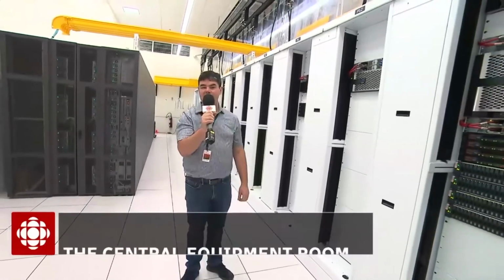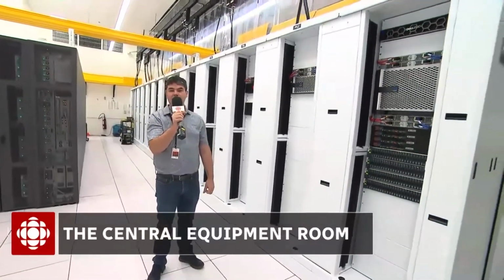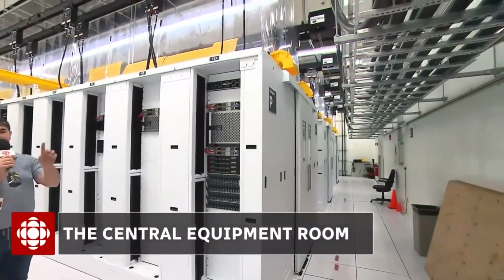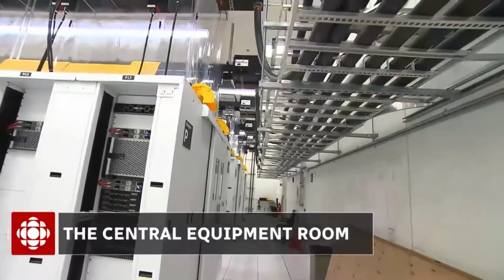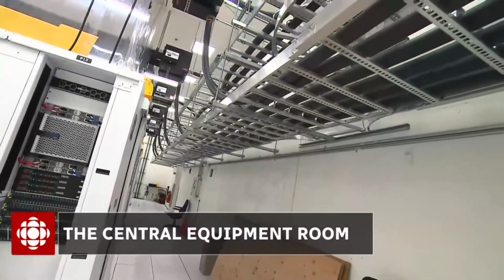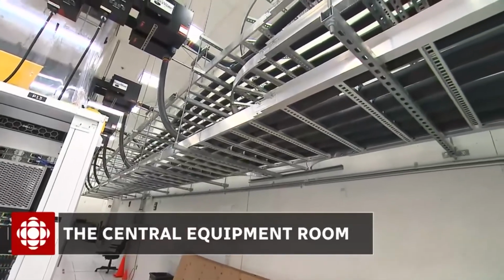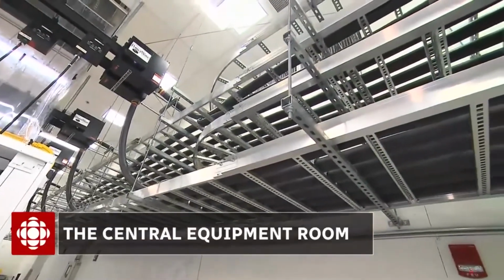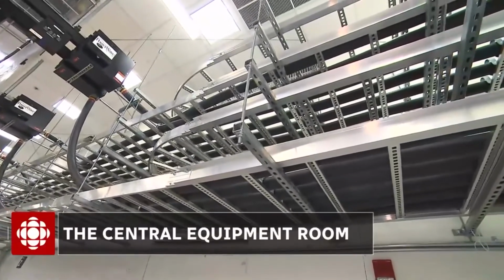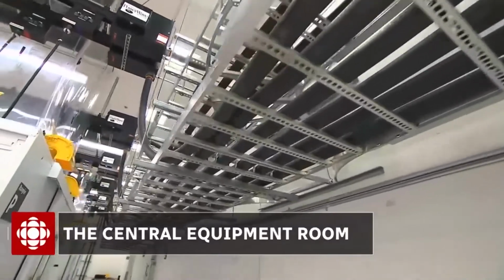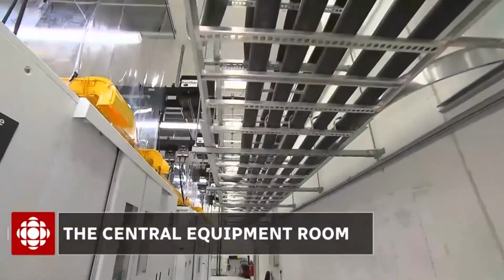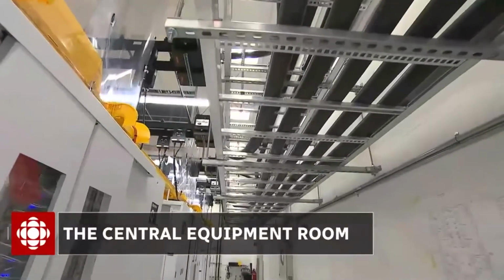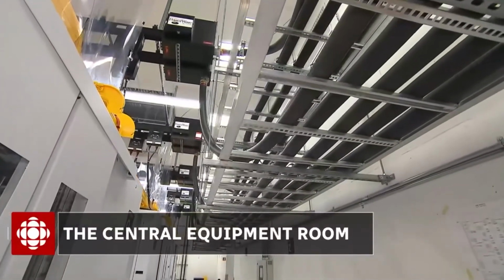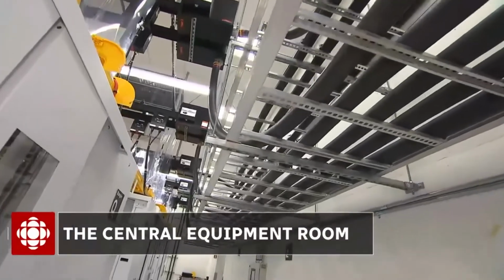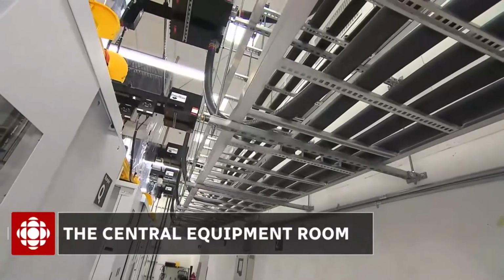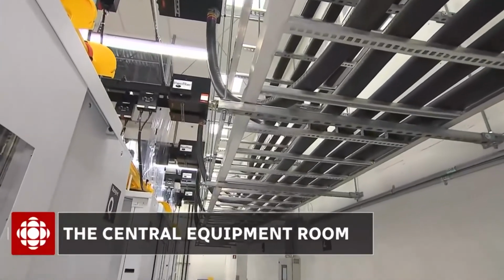This room is designed to accommodate up to 1 megawatt of technical equipment. You can see from above the electrical wire that brings the power. We have 2 generators for full redundancy, giving us 1 megawatt of usable technical power. Then we have 2 UPS, and after that, again, 1 megawatt of power available. The power then goes through the busways above the rack, which enable us to add or remove circuits to the rack without having to do any power shutdown.